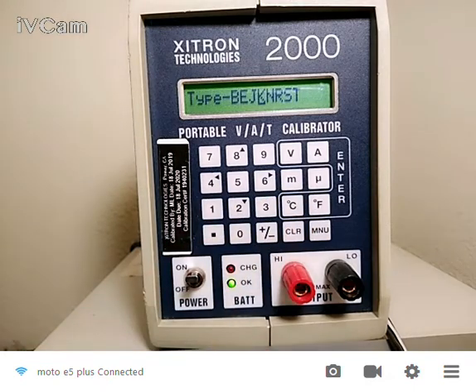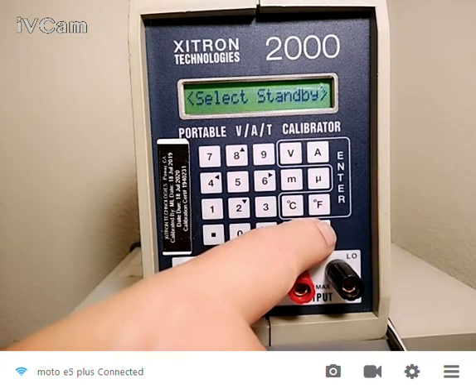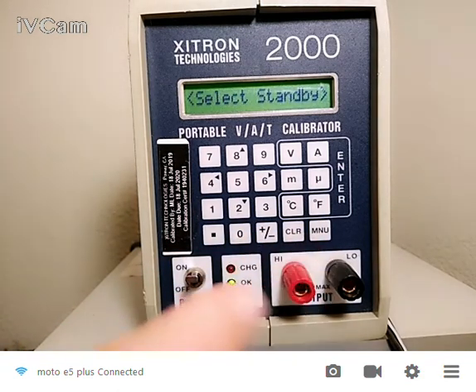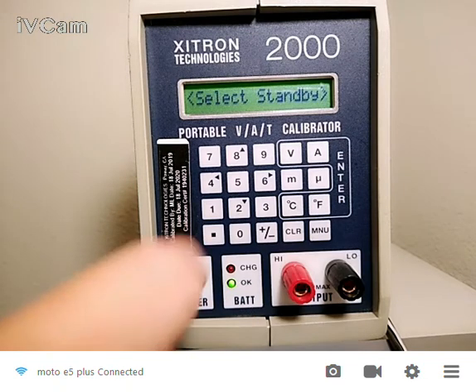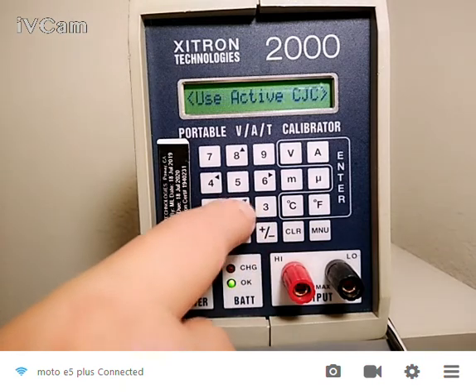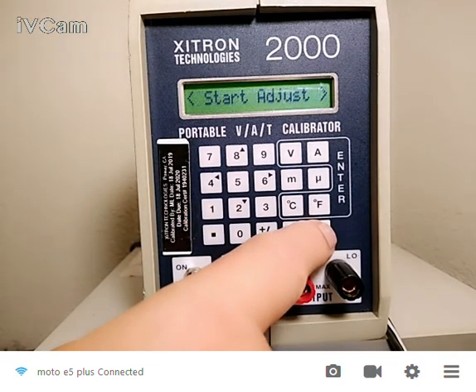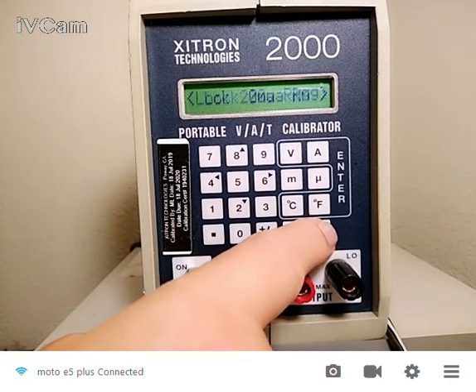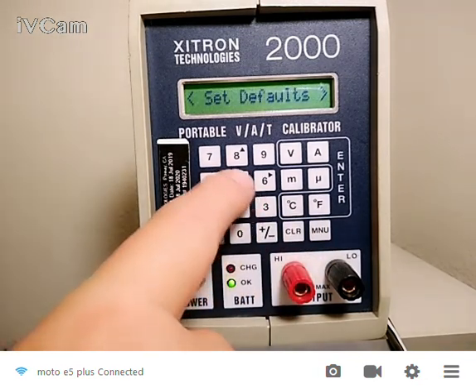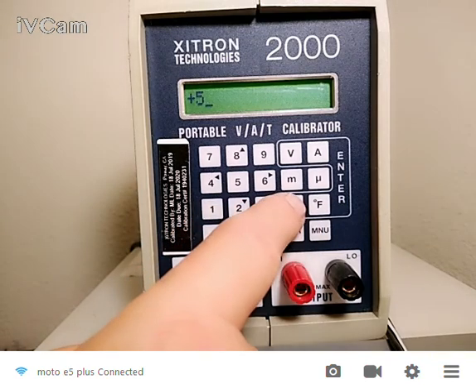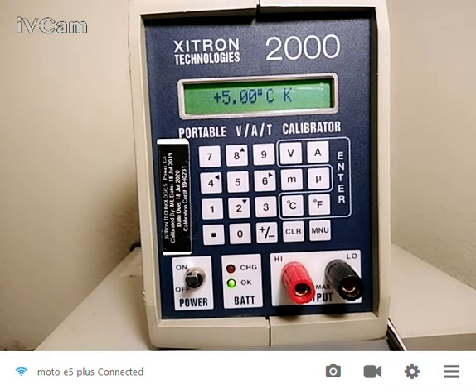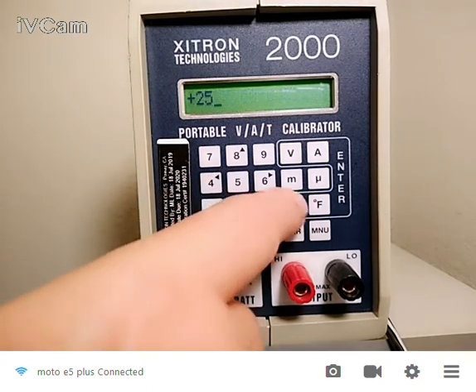Thermocouples: I'll hit enter, and you can see that we've got about 8 different types of thermocouples. Right now it's set for a K, but the main thing to know is we support all the popular types of thermocouples. And we're back to standby. So once you've gotten to this point, if you want to output something, all you do is hit, let's say, 5 degrees C, and now it's outputting the correct voltage to simulate a K thermocouple at 5 degrees C. If you want 25 C, there you go.